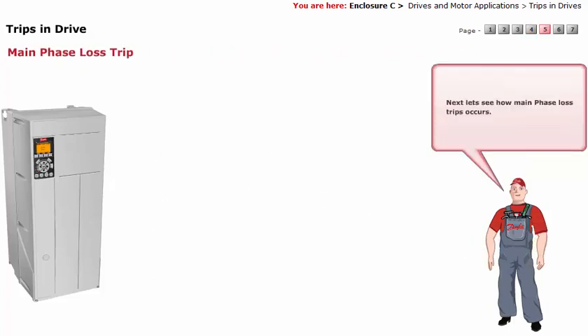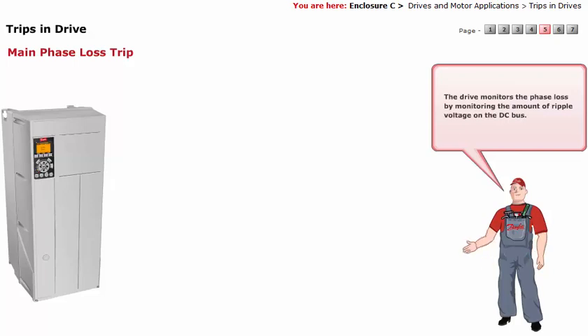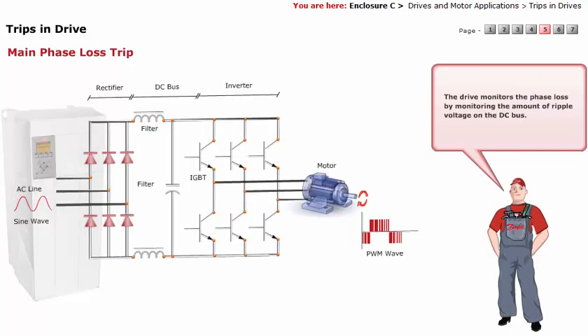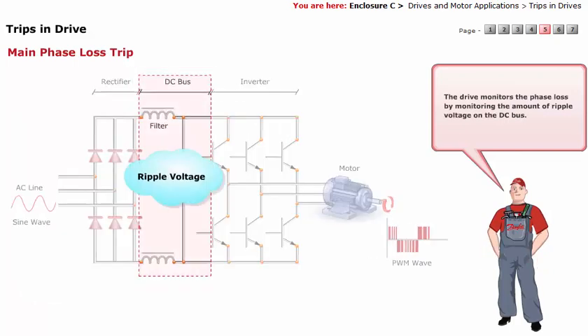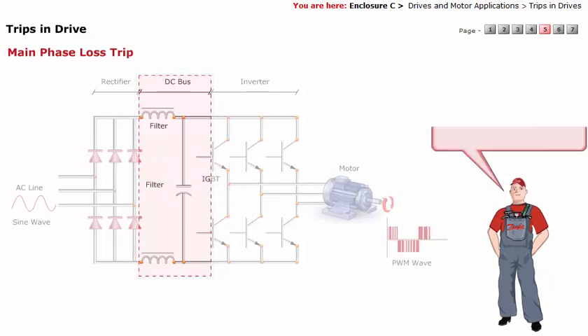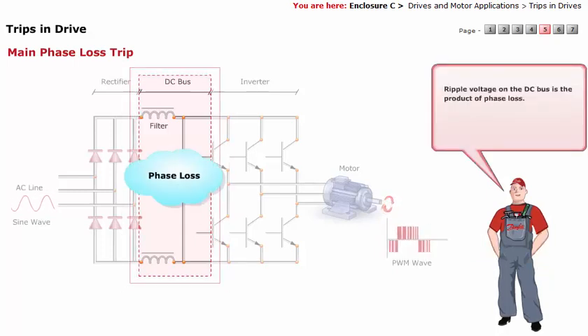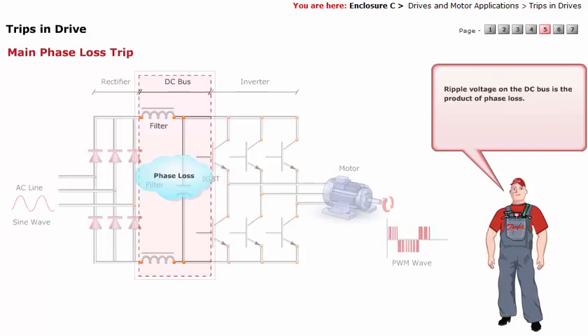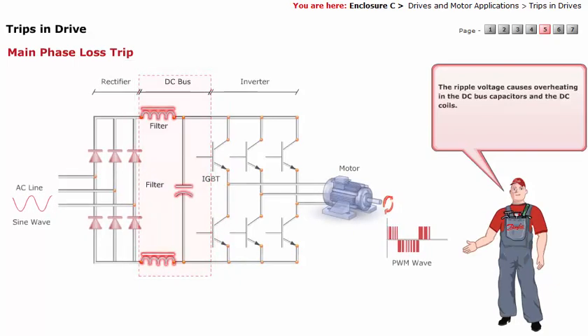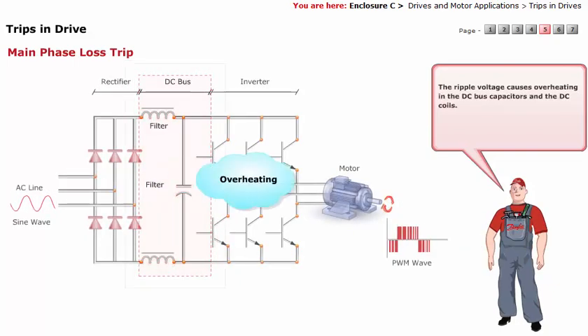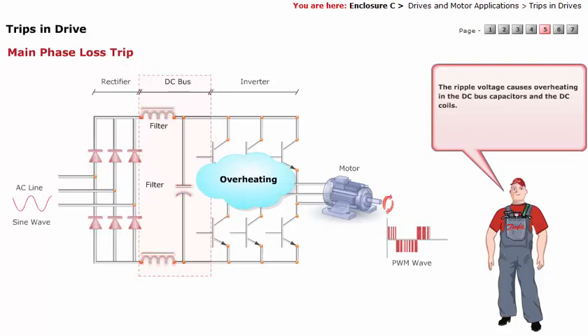Next, let's see how main phase loss trips occur. The drive monitors the phase loss by monitoring the amount of ripple voltage on the DC bus. Ripple voltage on the DC bus is the product of phase loss. The ripple voltage causes overheating in the DC bus capacitors and the DC coils.